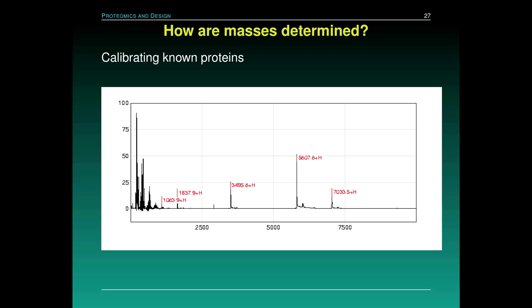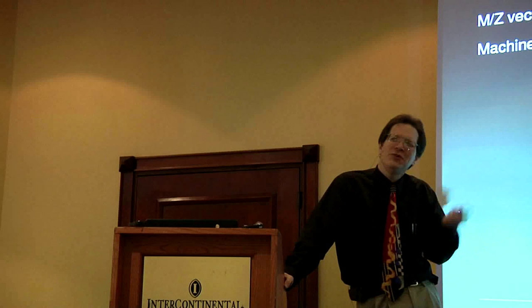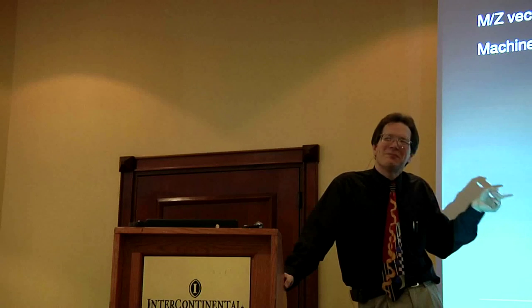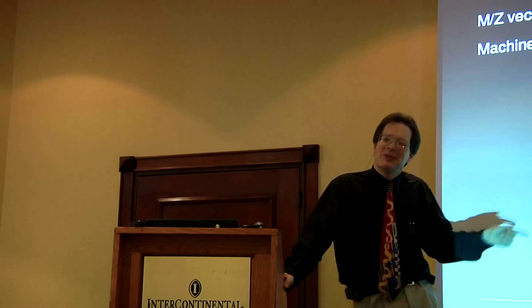Now, that said, what does it say to you that the spectra that they're producing are using the same calibration over 4 months of time? It says that they're not tuning their instrument that frequently. I've used these instruments. They're not that stable. As a matter of fact, we sort of get unhappy if we don't tune these, the SELDI ones, once every week or so.